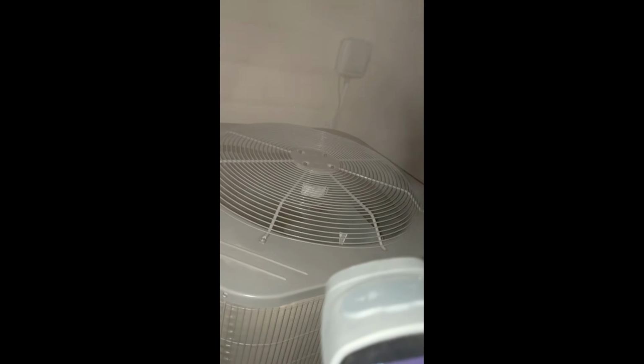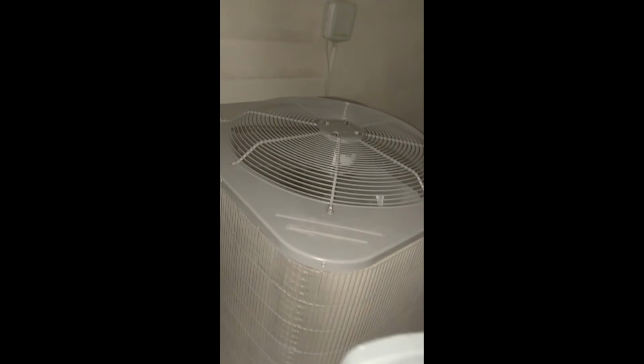From this last cold snap that we're just now coming out of, we had a lot of customers calling in asking about their heat pump. I hear a loud clunk or a whish noise, and then the system starts smoking. Is it going to blow up? Why is my system saying that the heat kits are running a whole lot longer than they normally do? My system doesn't seem to be heating right.